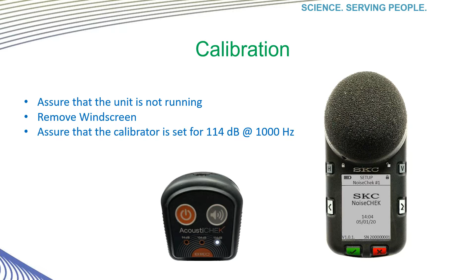A 5-second countdown will start, allowing time for the user to abort the calibration if they choose to. If the calibrator is not removed, the calibration will begin automatically after that 5-second countdown. The screen will now show calibration in progress. After about 3 to 5 seconds, the calibration will be complete. When the calibration passes, the screen will show pass, a before, and an after reading, as well as an adjusted value. And I want to go through these a little bit.